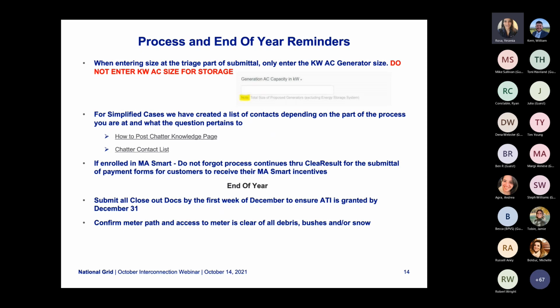If you have a battery on that system that is AC coupled, do not include that rating along with the generator rating in this section. Once you enter your generator kW AC capacity here, it will then ask if there's a battery, and at that point you'll be able to enter the rating for the batteries there.